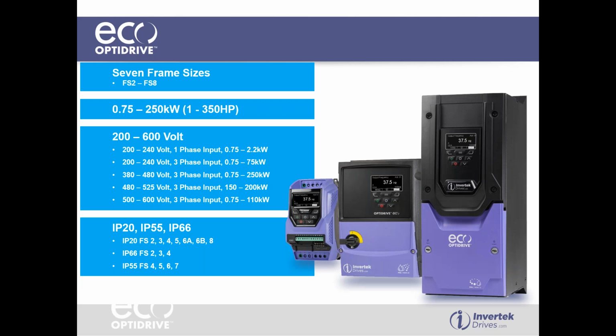So the frame sizes, we go from frame size 2 to frame size 8, and we have 3 different IP classes. So IP20 for drives mounted into control cabinets, IP55 for the bigger units, so we can mount them directly on a plant room wall or something like that. And then we've also got the outdoor rated IP66 units.